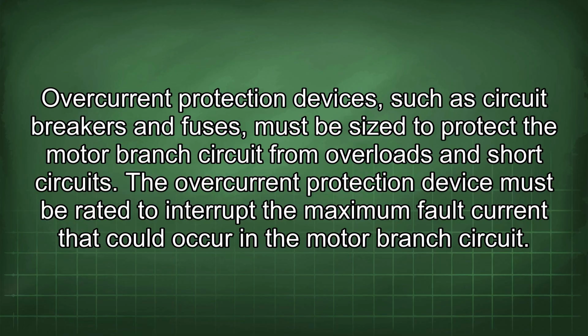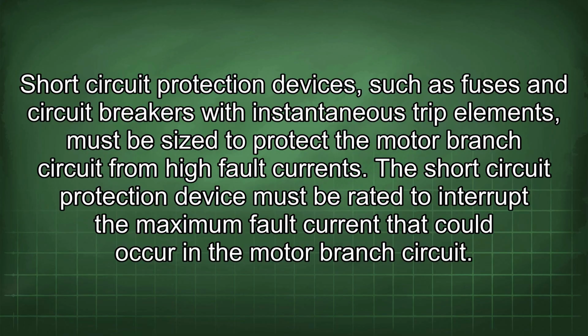The overcurrent protection device must be rated to interrupt the maximum fault current that could occur in the motor branch circuit. Short circuit protection devices, such as fuses and circuit breakers with instantaneous trip elements, must be sized to protect the motor branch circuit from high fault currents. The short circuit protection device must be rated to interrupt the maximum fault current that could occur in the motor branch circuit.